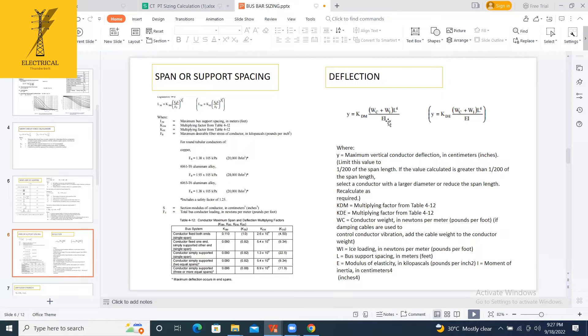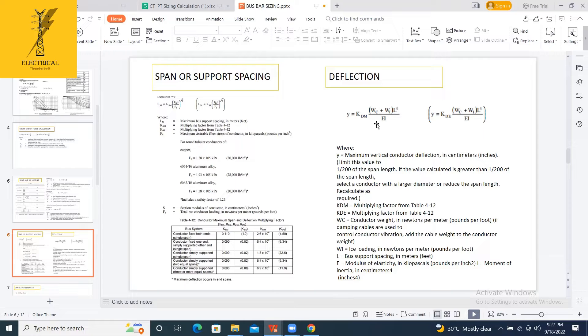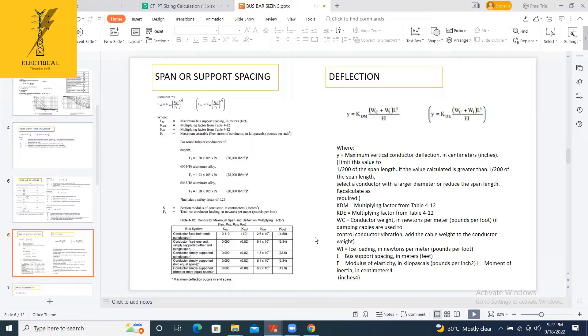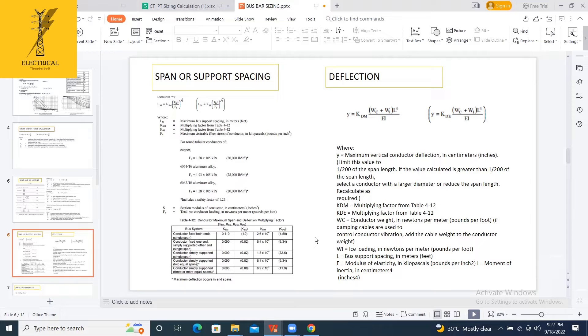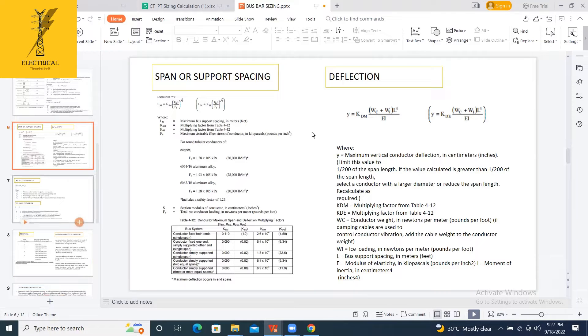Again, it depends upon one more factor, the modulus of elasticity, and the factors of KDM. That again depends upon how you connected the conductor, whether fixed at both ends, fixed at one end, support at one end, both sets are only support. It depends upon that. After calculating the deflection, we are going to calculate the cantilever strength.